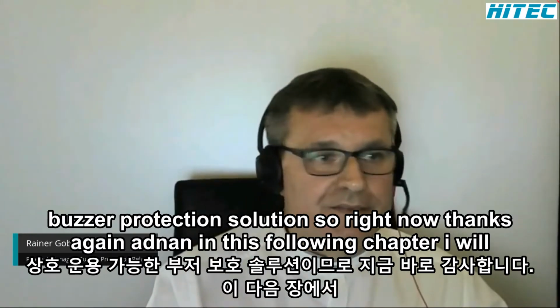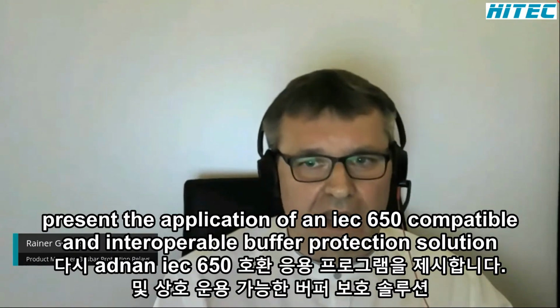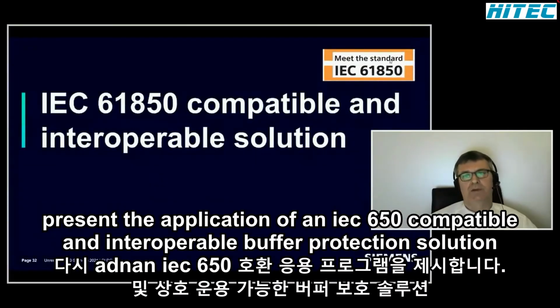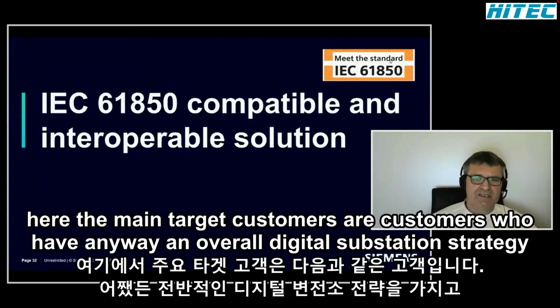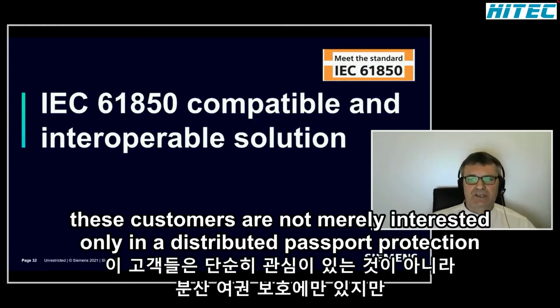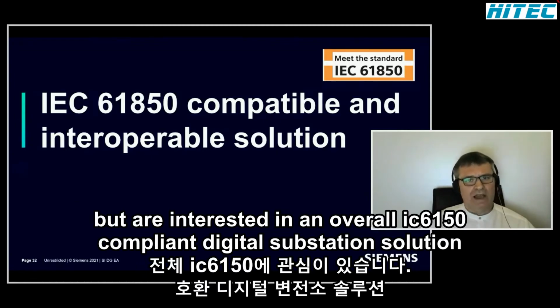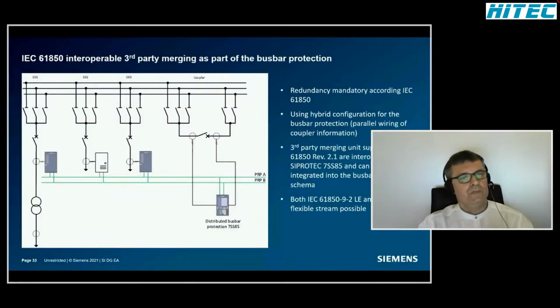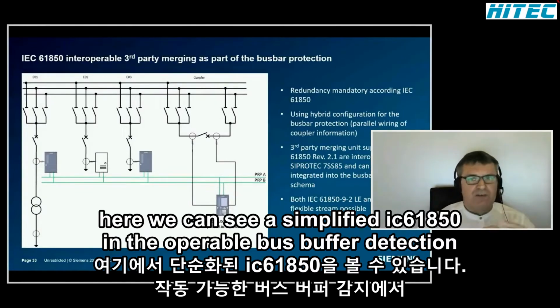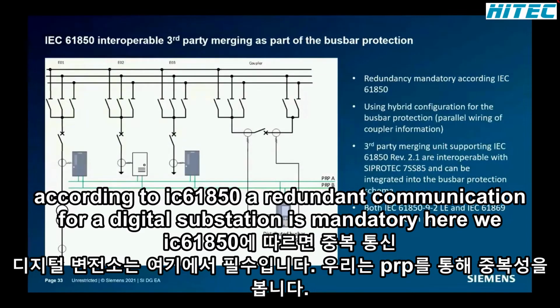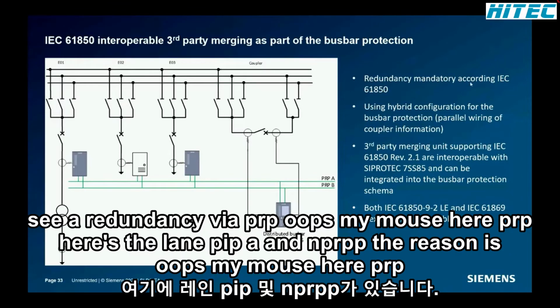Thanks again, Adnan. In this following chapter, I will present the application of an IEC61850 compatible and interoperable busbar protection solution. Here, the main target customers are customers who have anyway an overall digital substation strategy. These customers are not interested only in a distributed busbar protection, but in an overall IEC61850 compliant digital substation solution. Here we can see a simplified IEC61850 interoperable busbar protection. According to IEC61850, a redundant communication for a digital substation is mandatory. Here we see a redundancy via PRP.